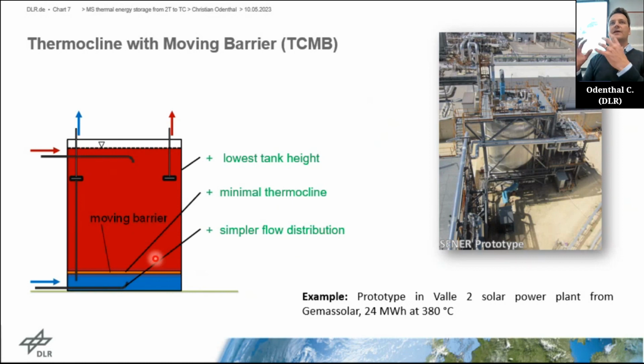But because you have a better insulation between the hot and the cold layer, you actually don't use molten salt as insulation. You can again reduce the complete height of the tank a little bit. And also, you have to care less about any possibilities of mixing effects during the operation. There's also been in this Valle 2 solar power plant a demonstrator, but there's very little information available about the outcome of the project. And we tested something like this also at DLR, but we had some issues with the moving barrier. So yeah, we didn't get any cyclic operational results from that.